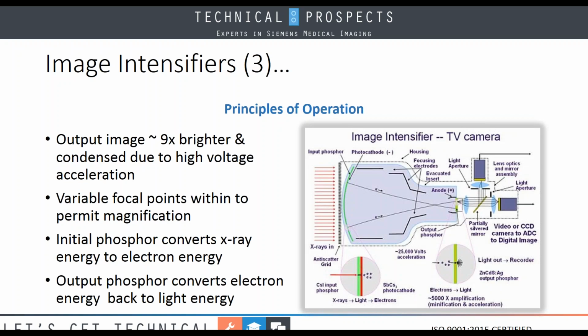In looking at the principle of operation here, that acceleration of these electrons due to the high voltage will generally make the output of our top output screen at least 9 times brighter than the overall input screen. The circuitry also allows for various focal points to permit magnification.